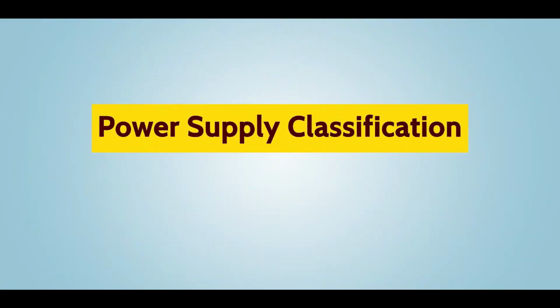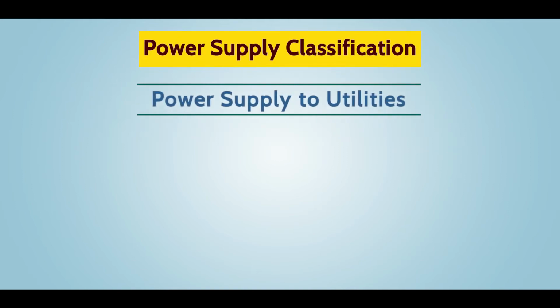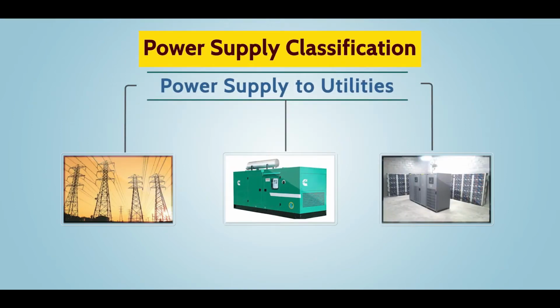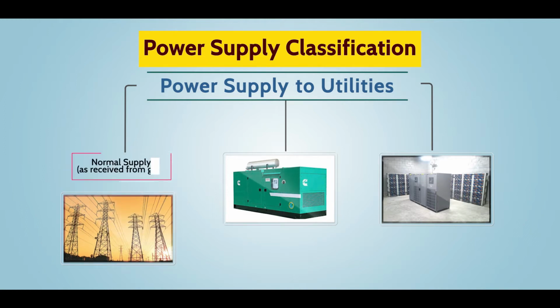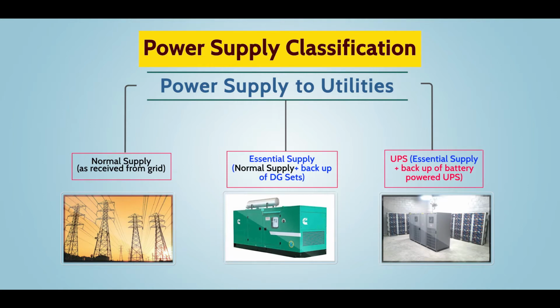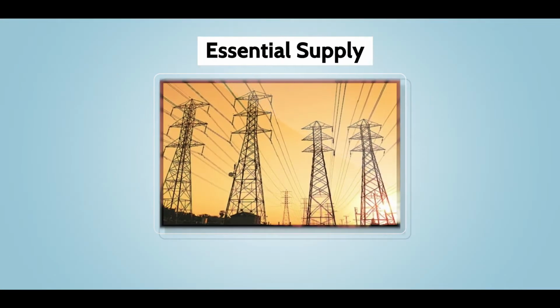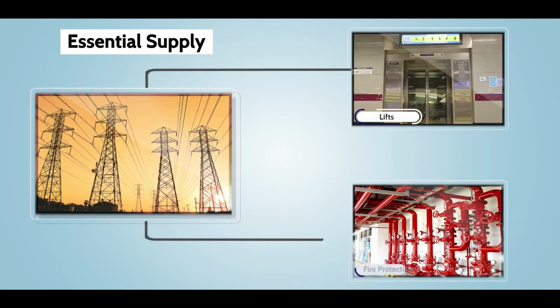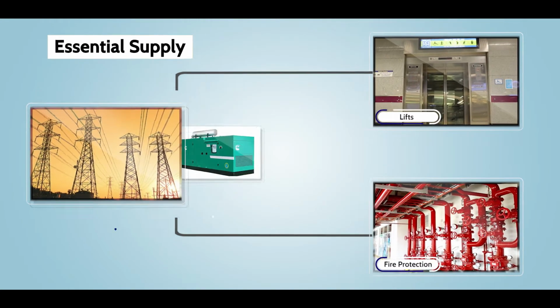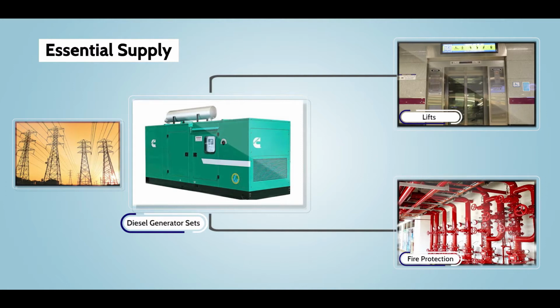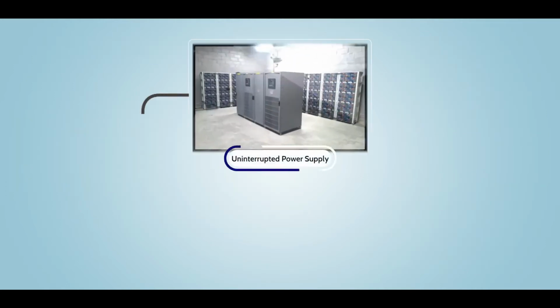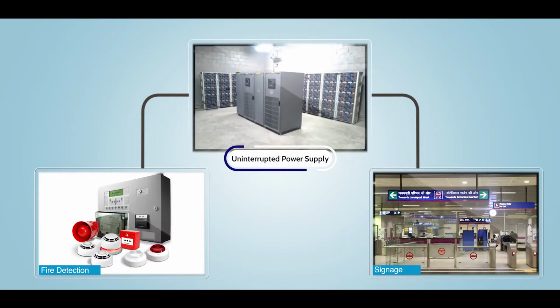Requirement of electrical power supply is different for different utilities, not only in terms of load but also in terms of availability of backup. Power supply to utilities can be classified into three categories: normal, essential, and UPS. Power supply requirement for some utilities like lift and fire protection are essential, and hence for them power backup of diesel generator set is made available. Certain utilities like fire detection and signage require an uninterrupted power. The same is made available through battery-supported UPS.